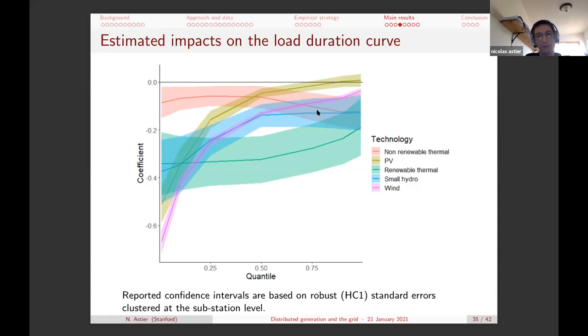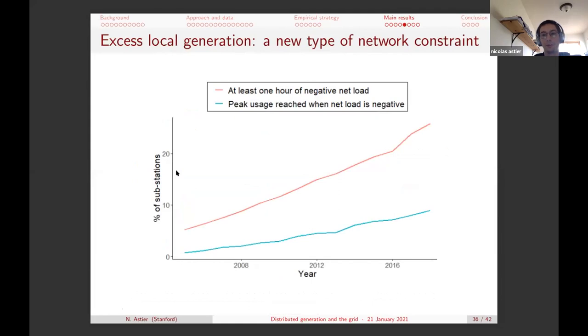And the other interesting feature we get from this graph is on the other side of the distribution, in the lowest quantile, where we see this very large impact on the bottom quantile. So PV, wind, but also small hydro and renewable thermal, they tend to decrease the lowest quantile of the load duration curve, which historically didn't matter that much, but starts to matter a little bit and will matter more and more. And the reason is that as these bottom quantiles decrease, the net load as seen by the transmission grid becomes negative. So locally there is more generation than consumption. So you start having backfeeding hours. So power flowing from the distribution grid to the transmission grid.